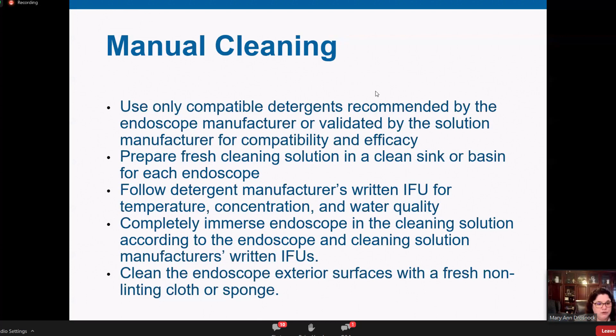As far as cleaning brushes go, in line with what FDA and other professional societies say, you want to make sure you're using a brush that meets the guidance from the endoscope manufacturer. I'm not saying you have to use that exact model of brush, but if you don't use that model, then you want to make sure it matches those characteristics of that brush as far as length or width of the bristles and all of that. We don't require that they have to be single-use brushes, although I will tell you that the majority of facilities are using single-use brushes. But if you're not, then the brushes themselves must be cleaned and disinfected or sterilized in between uses.